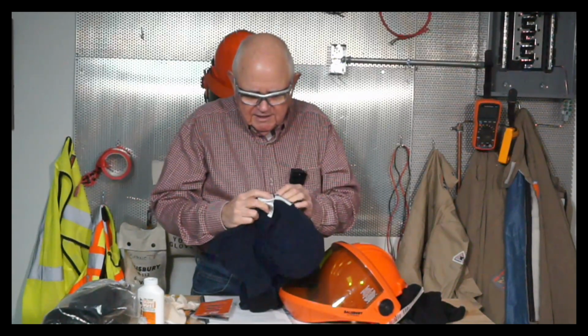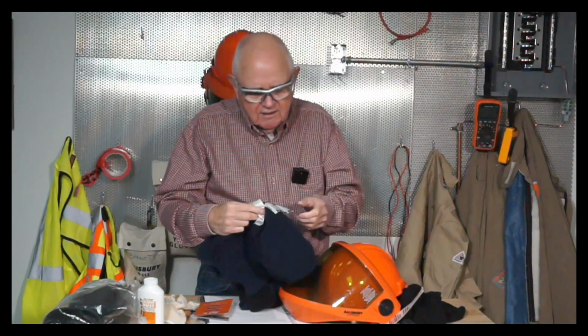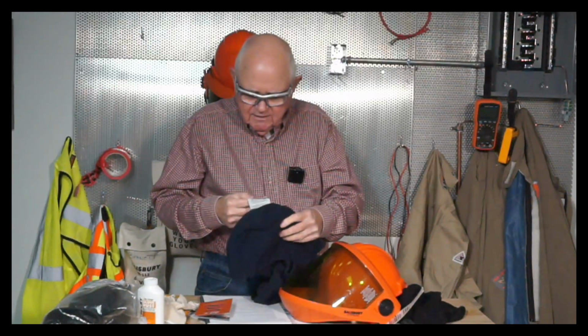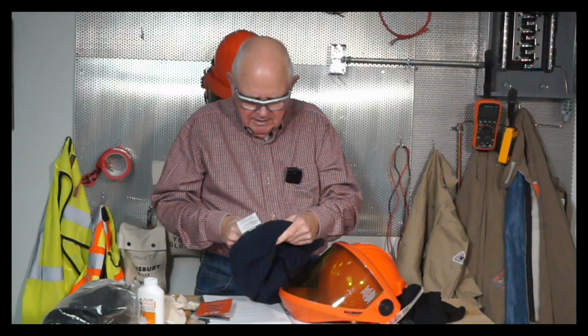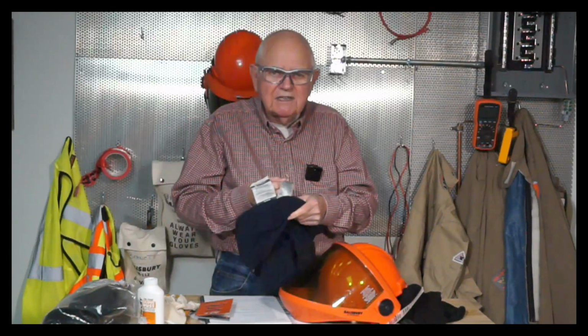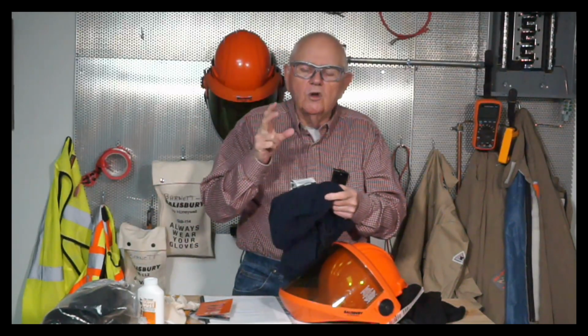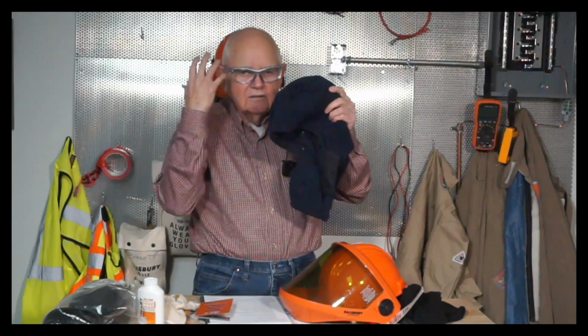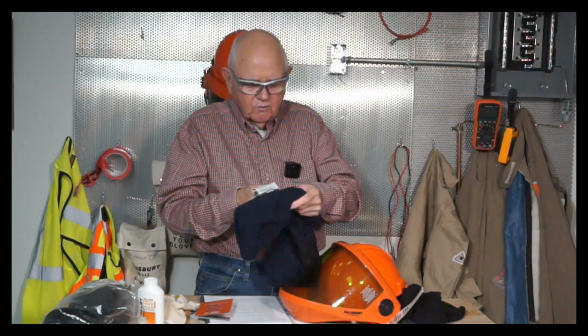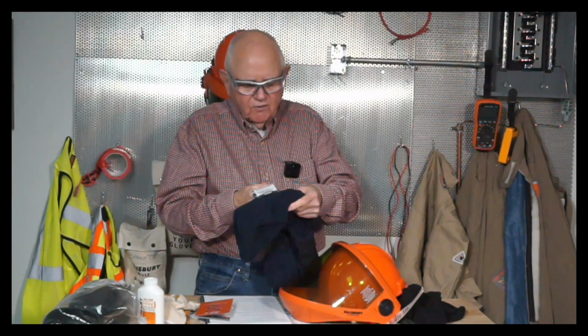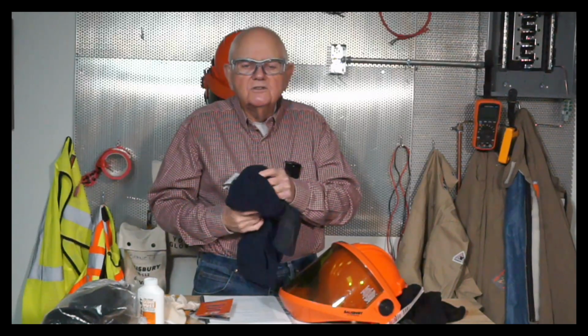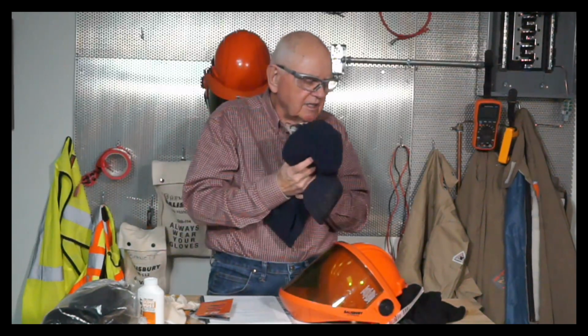That's okay. It says EBT. And let's see, where did that go? There it is. EBT, the energy break open threshold value for this particular hood to wear over and to wear in the winter has a rating of 34 calories per centimeter square. So it's rated for 34 calories, the EBT. So I can use either the EBT or the ATPV rating. 99% of the time, I bet you're going to see the ATPV rating out there.